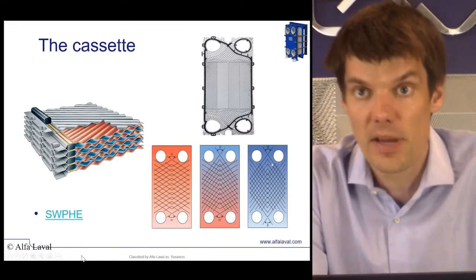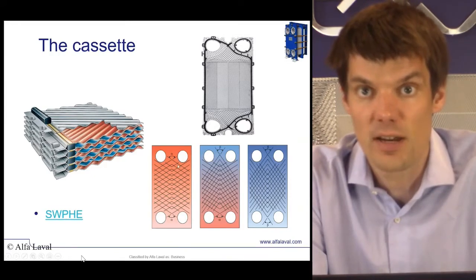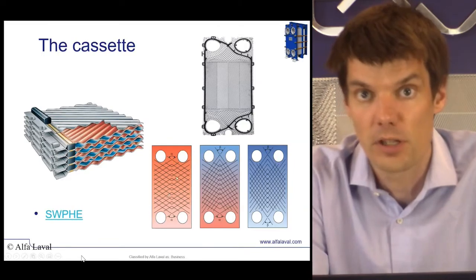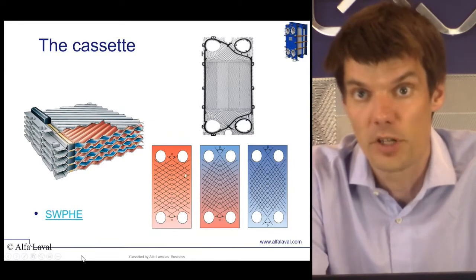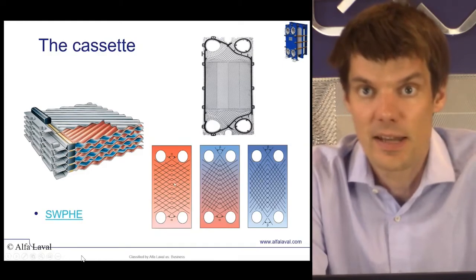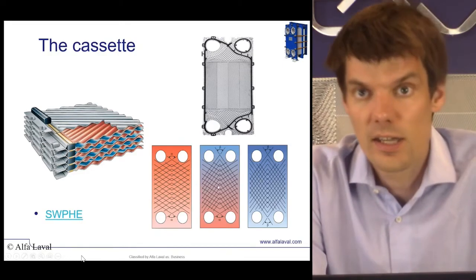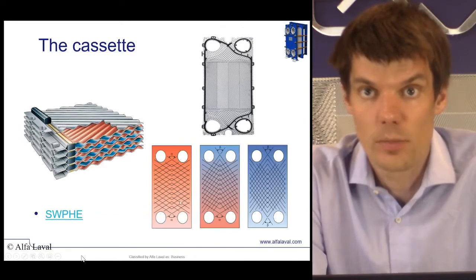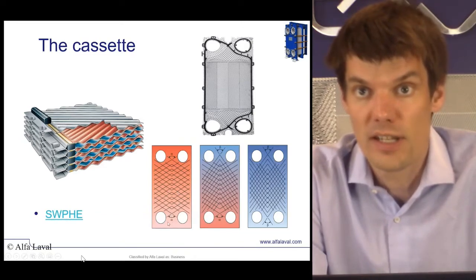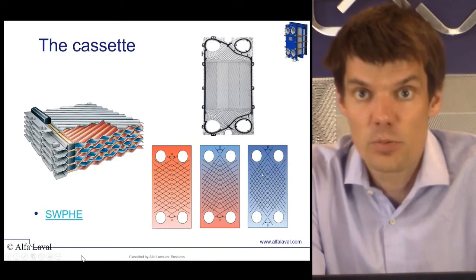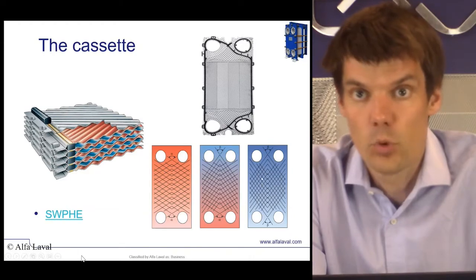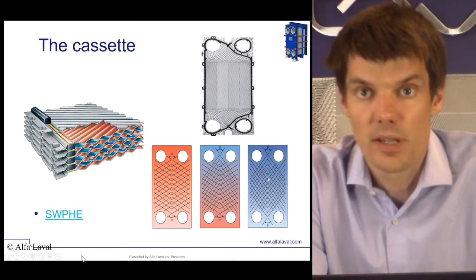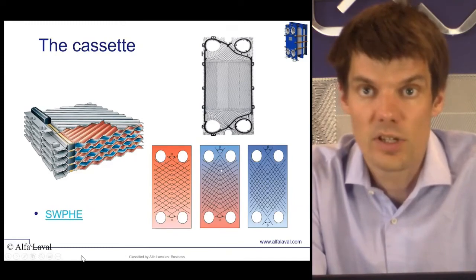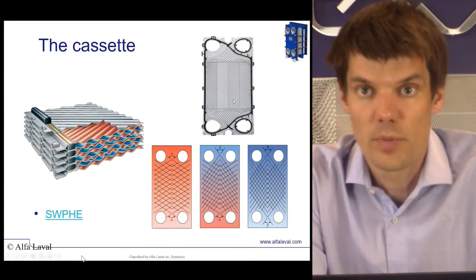By changing the pattern of the plates, in most cases by changing the herringbone angle, channels with different thermal and hydraulic characteristics can be formed, optimizing the design against any type of application. In short, the lower the angle of the herringbone is, the lower the pressure drop, but also the lower the heat transfer. On the other side, plates with a higher angle of the herringbone would generate more pressure drop, but also more heat transfer. Then there is a third alternative to combine two plates, one high and one low, and then we get some sort of intermediate performance.